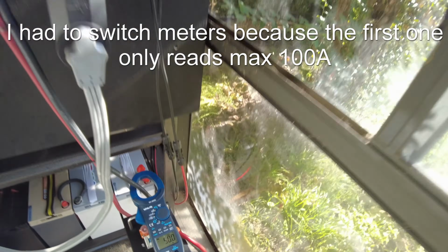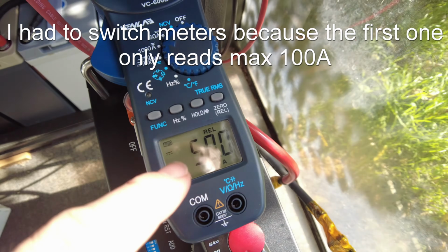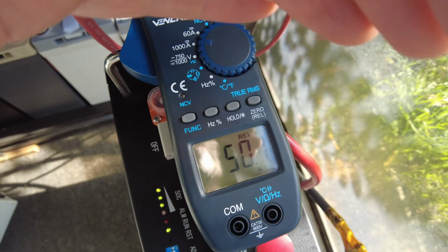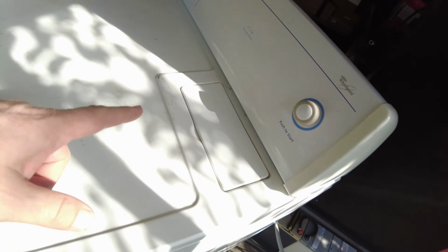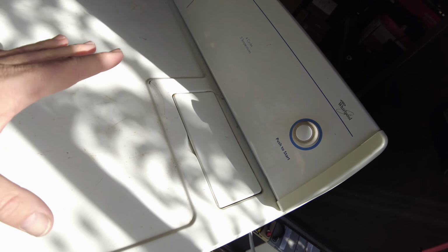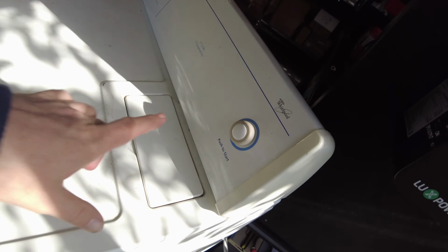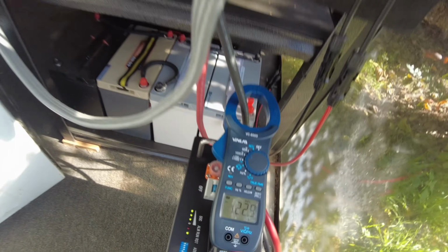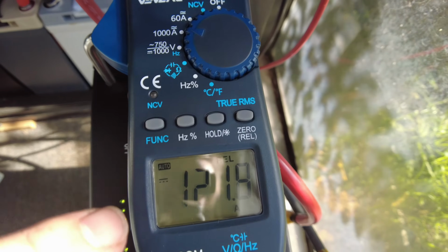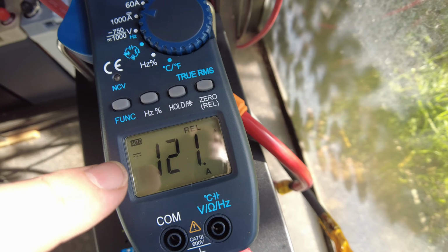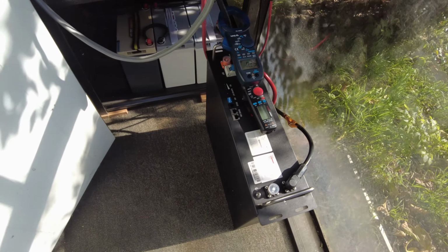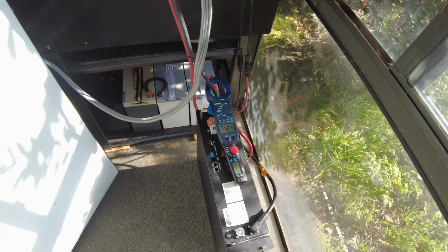So let's try to run the dryer again. All right, so we're already pulling 50 amps, and that's because the dryer is actually broken. It actually runs and burns power without being on, that's why I had to replace it. But if I turn it on, yeah, I see we're pulling over 100, we're pulling 121. So I'm going to turn it off because it'll make this trip again.